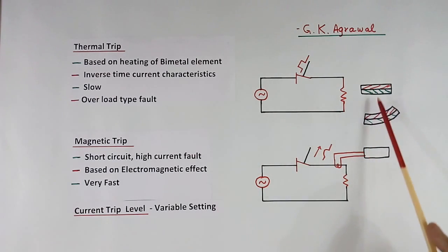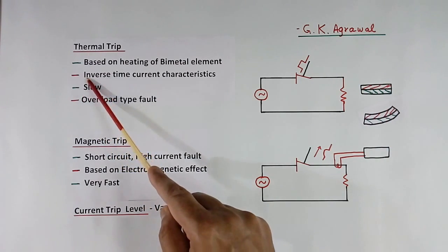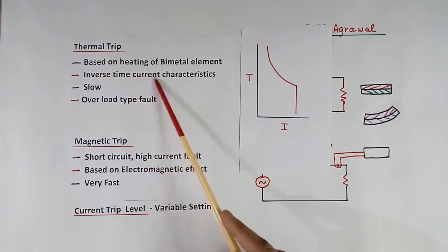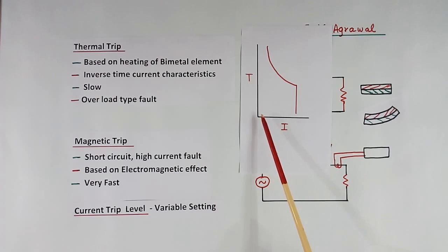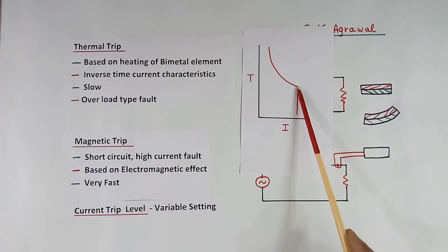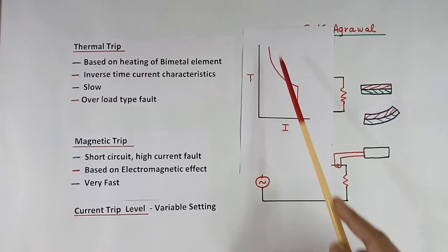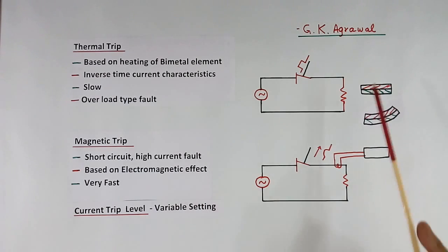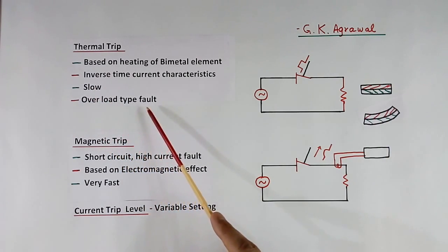Because this is heating based, it is very slow and has inverse time-current characteristics. If current is increasing, trip time is decreasing, because with more current it will heat faster. Because of heating it is slow, and it works when overload comes.